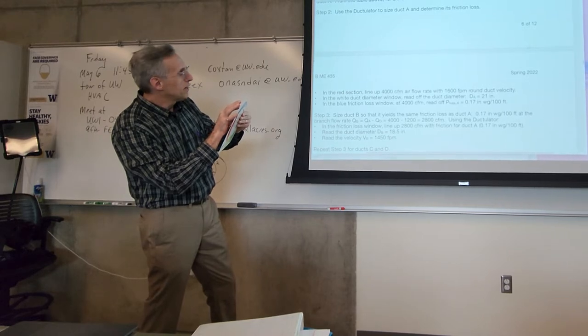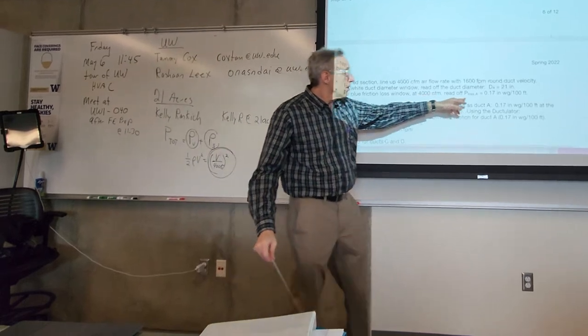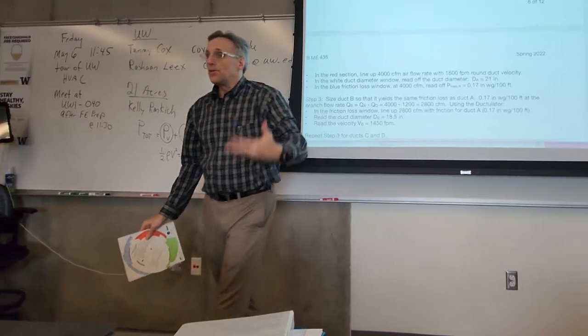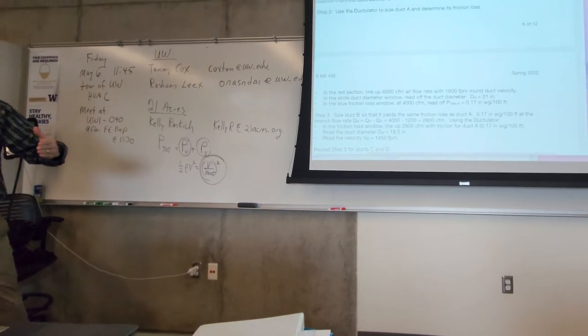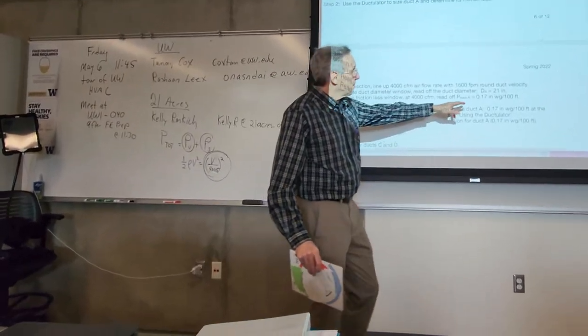0.15, 0.17, or 0.18, 0.17, that's a little high, actually. Nowadays I might want to go to a bigger duct, drop that pressure down a little bit. But for now, we'll take that 0.17.